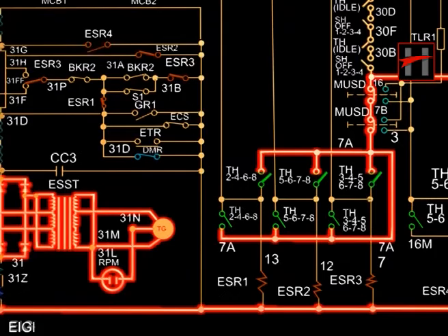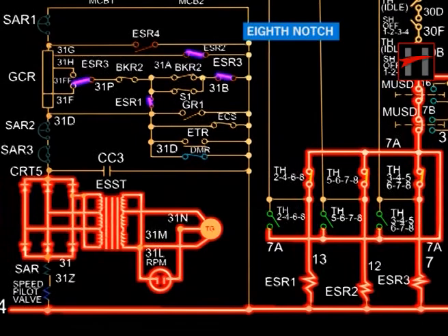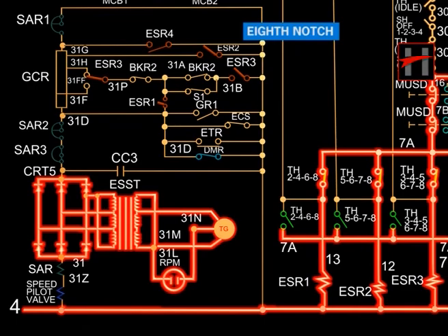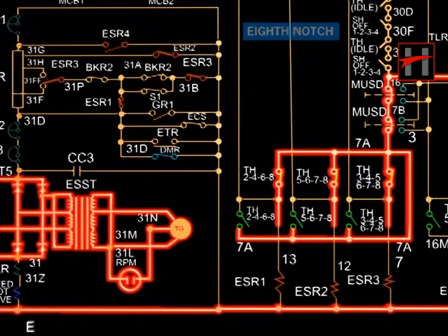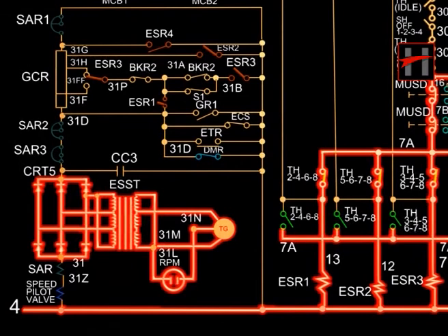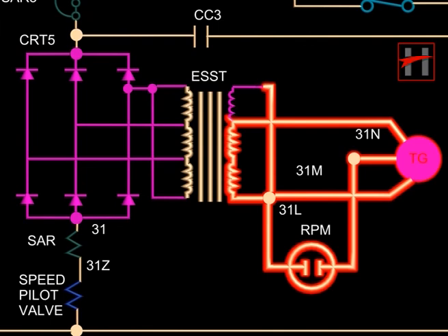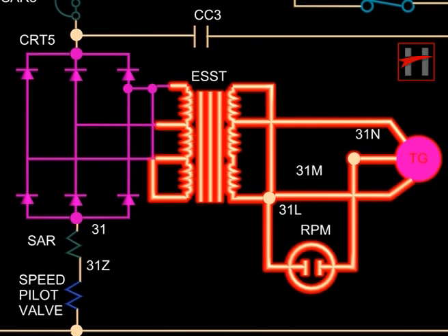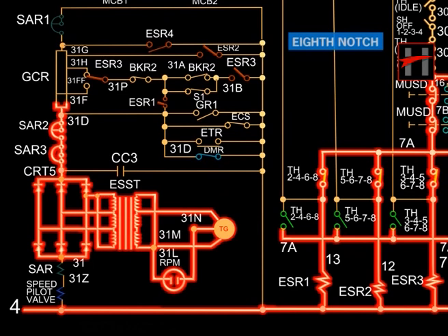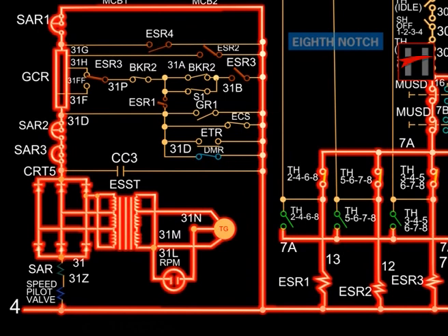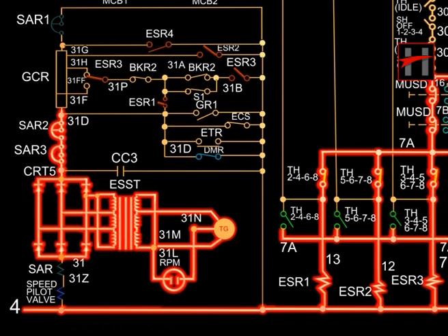In the eighth notch position, ESR-1, ESR-2, and ESR-3 get energized. The normally closed interlock of ESR-1 opens due to energization of ESR-1. The interlock of ESR-3 changes position from 31F to 31FF and the normally closed interlock of ESR-2 opens. The rectified output of the tacho generator energizes CRT-5, SAR-3, SAR-2, GCR, SAR-1, and returns via cable number 4, speed coil of pilot valve, cable number 31Z, SAR coil, and cable number 31.